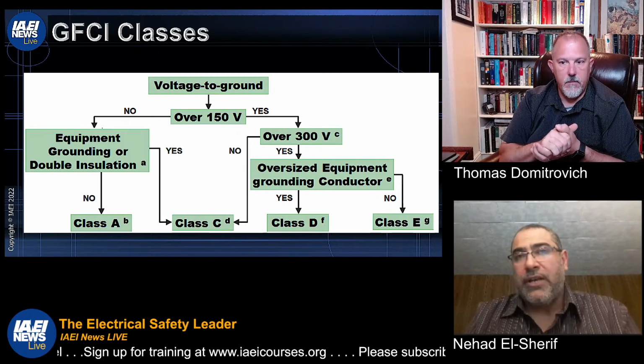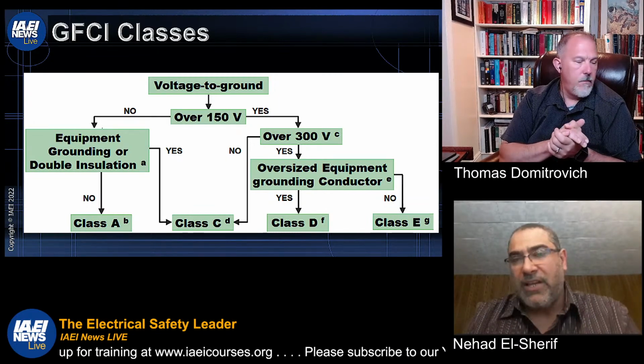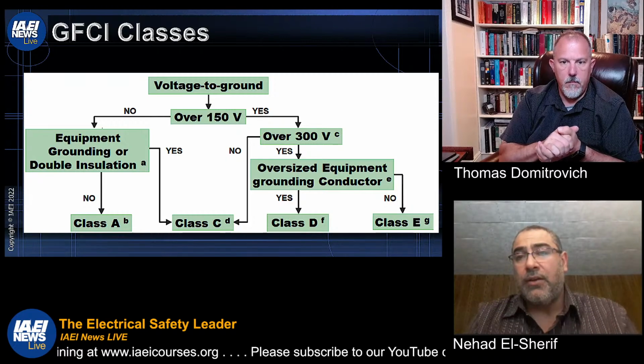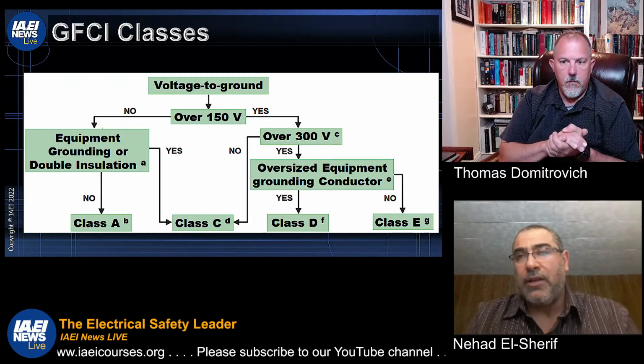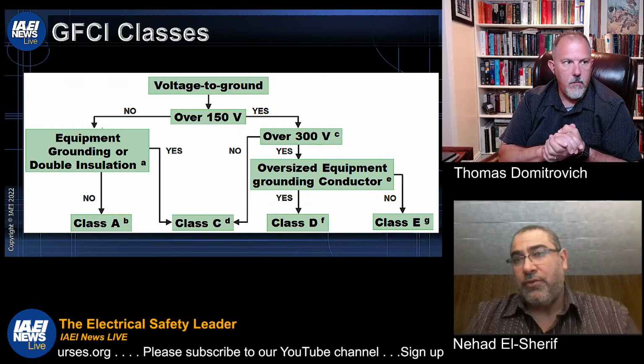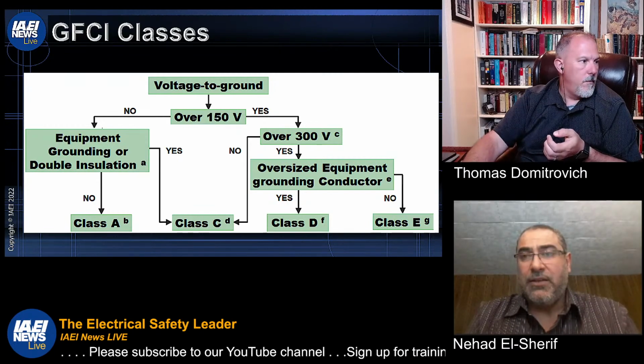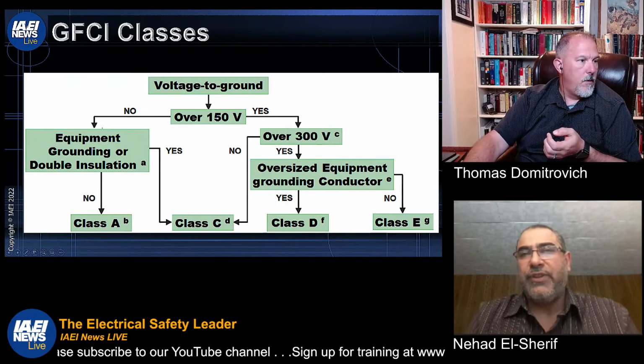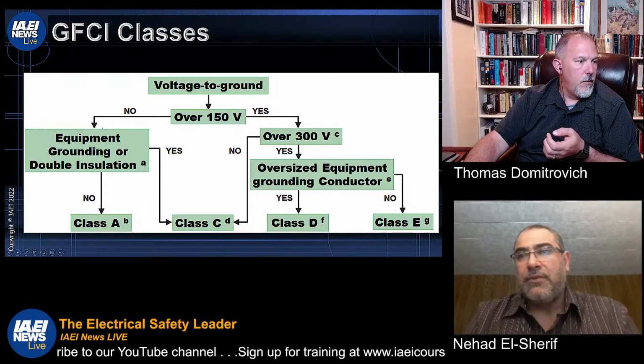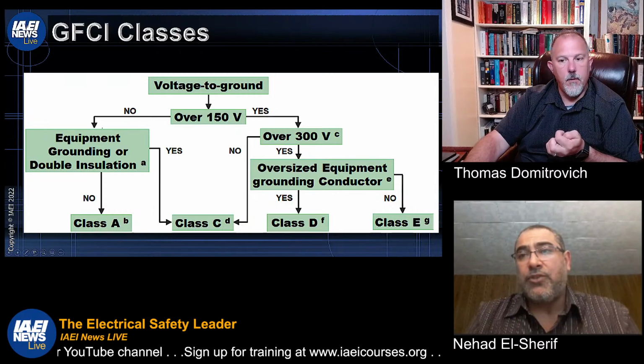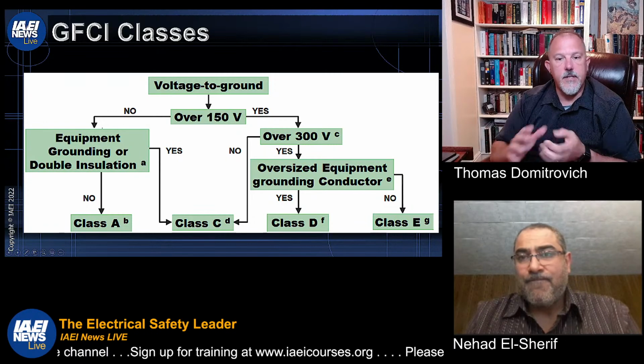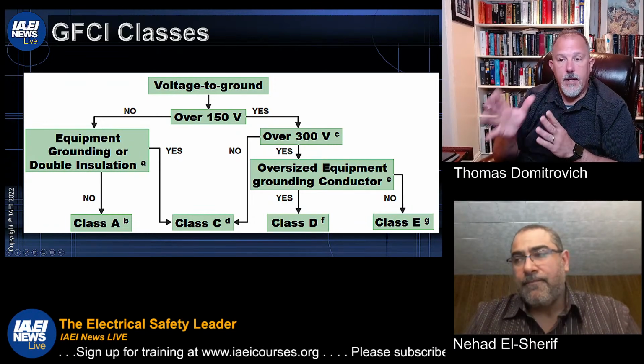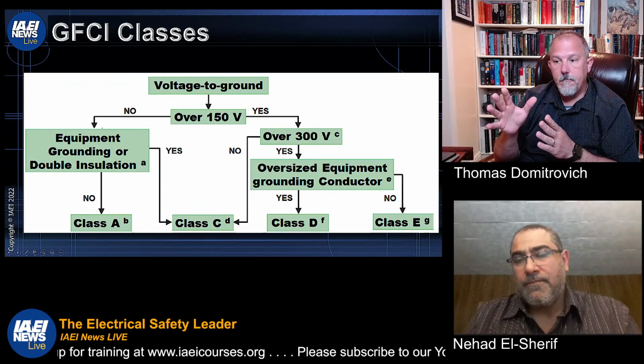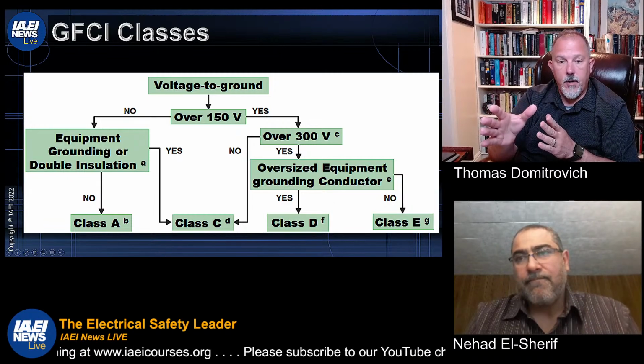Again, excellent. For our US viewers, Class D is mainly for 600 volt line-to-line systems, so it shouldn't be a concern. Most likely you'll be using a Class C. Class D is mainly for those very limited systems, mainly in Canada and very limited in the US, that have a 600 volt system. Excellent. So here in the United States, now we're going to get into, okay.